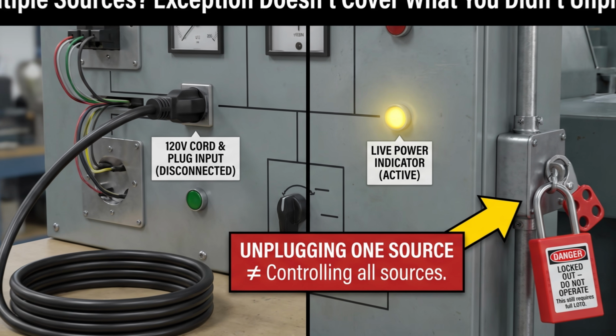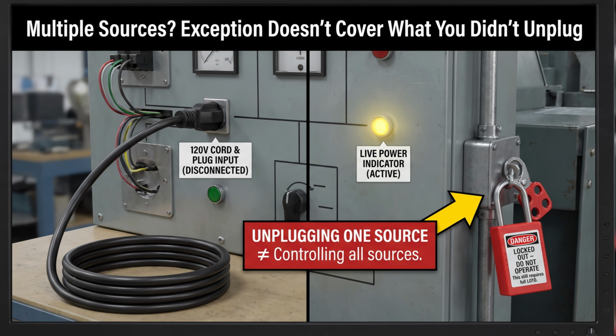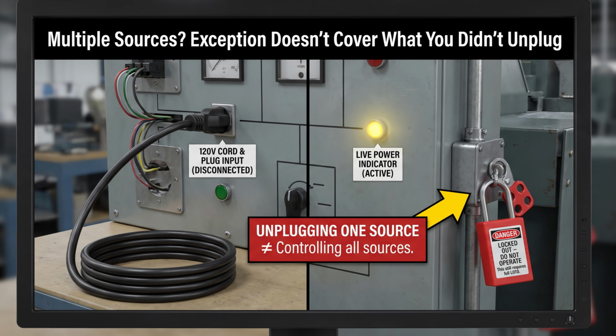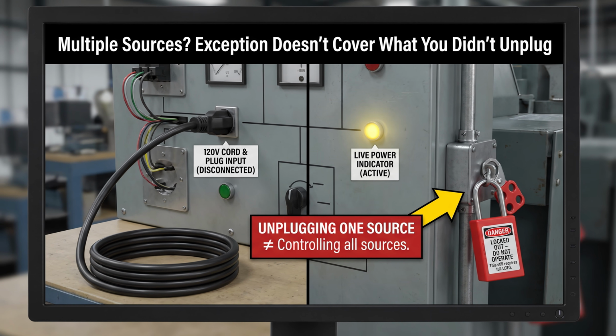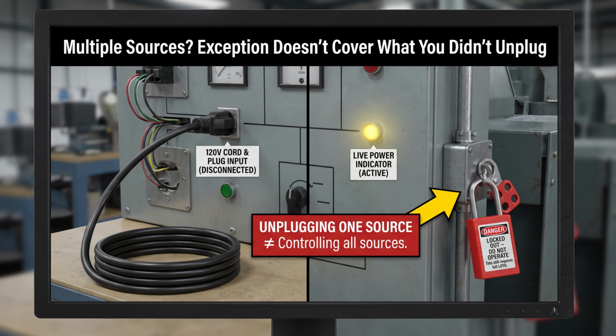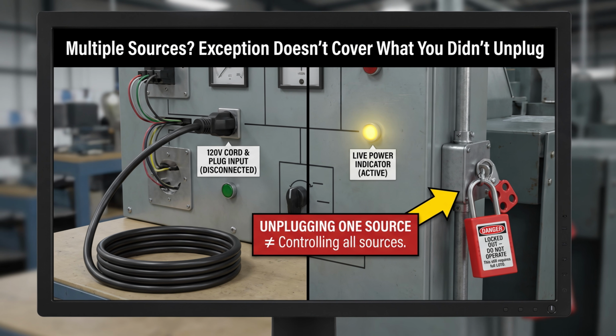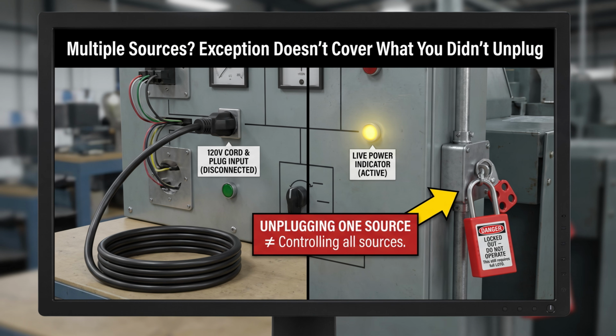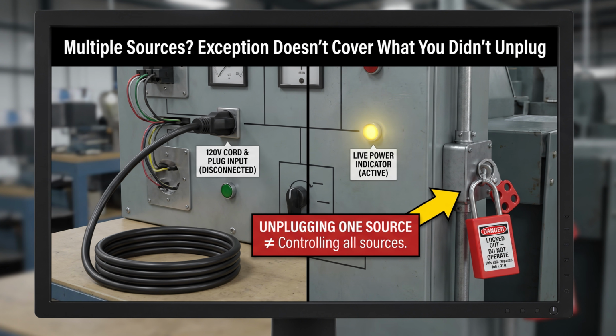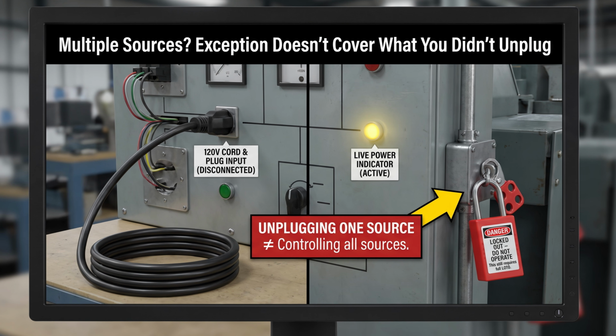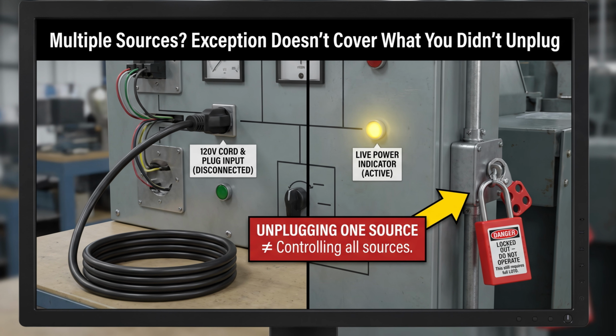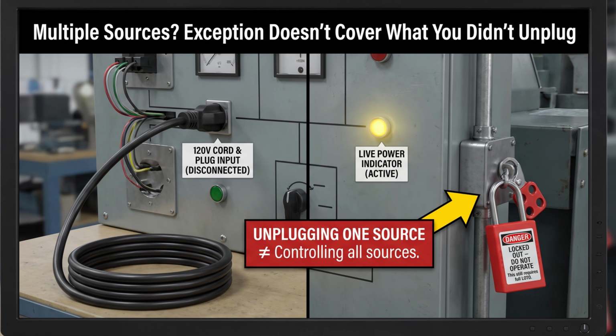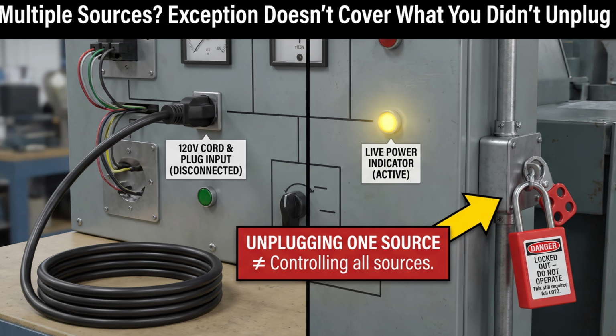The cord and plug exception fails immediately in several situations. First, if the equipment has multiple power sources. Some industrial equipment has both a cord and plug for controls and a hardwired motor, or 2 separate cords. Unplugging one does not control the other. You must identify and control every source. If any energy source cannot be controlled by a plug under your exclusive control, full lockout procedures are required for that source.